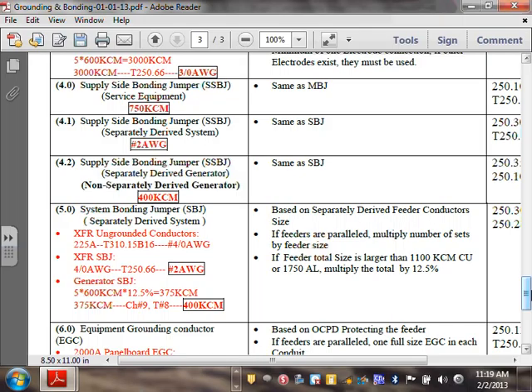It's called system bonding jumper by the code for a separately derived system. For the transformer, it's based on the separately derived system conductors, exactly like the service. Instead of basing it on the service conductors coming to the service entrance, now we base it on the conductors coming out of the transformer. If you parallel them, you have to multiply by the sets, and also you have to apply the 12.5%. So for all practical reasons, you're really sizing a main bonding jumper with a different name. That's it. No difference really in the arena.